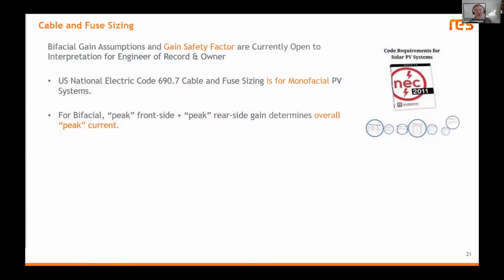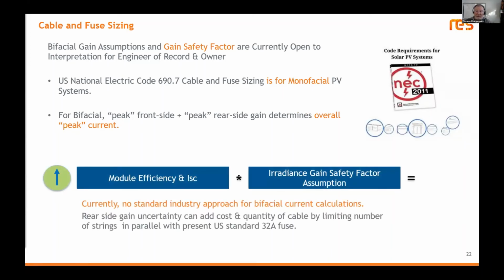But it doesn't end there. The one very tricky part is what we call cable and fuse sizing, because from an engineering point of view, you have to build in a gain safety factor. And that today is open to interpretation for engineers. Why is that? Well, because in the USA, NEC code 690.7, which governs cable and fuse sizing, is for monofacial PV systems only. So for bifacial, you have to take the peak front side and add the peak rear side gain to determine the overall peak current. So you have to know all that in order not to run into a mismatch.